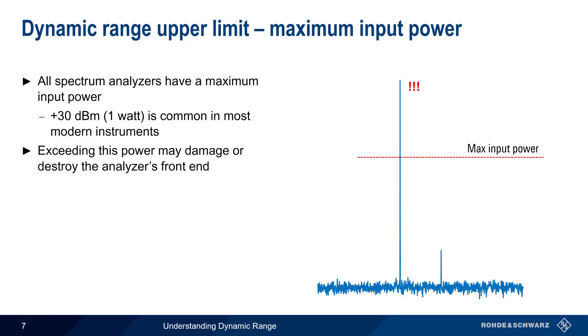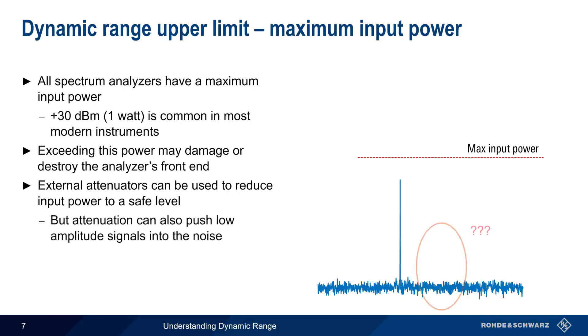If signals with a power greater than this level need to be measured, external attenuators are a simple and reliable way to reduce input power to a safe level. But note that this attenuation can also push low-amplitude signals beneath the noise floor. The internal active components used in spectrum analyzers, such as mixers and amplifiers, also limit the upper end of dynamic range.